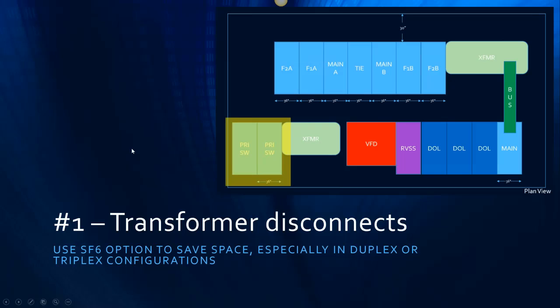Now, the first item we're going to take a look at to try to see if we can't save some space are the transformer disconnects. And I've highlighted them here on the drawing. And we're going to use a mechanism that I stumbled across about 7, maybe 8 years ago when we did a project with Siemens. And it was actually for the Gigafactory out in Nevada, not far from Las Vegas. And we used a 35 kV mechanism in that case, and those sections were only 20 inches wide.